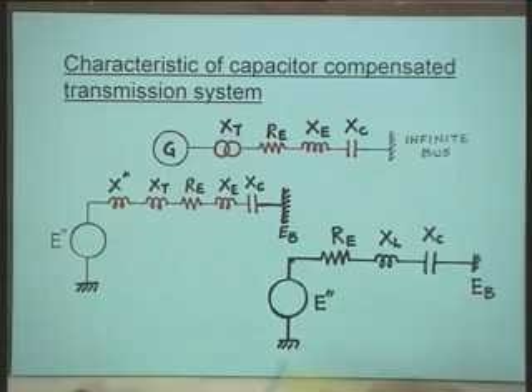When a fault occurs in this series compensated system, the fault currents will also have components of frequency corresponding to the natural frequency of the inductance and capacitance of the system. You all know that when an RLC circuit is excited, the current which flows will have a frequency of oscillation which depends upon the inductance and capacitance of the circuit. The capacitance you put in the circuit is to partially compensate for the line reactance at power frequency. Therefore, at a frequency less than the power frequency, at a subsynchronous frequency, these two reactances may become equal, and at that time we say that series resonance occurs.